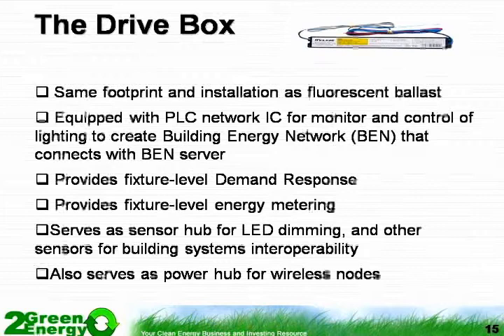We'll have a tiny logic power supply that will drive the PLC chip, as well as provide power to other sensors that we can plug into with Ethernet standard RJ45 connectors. And so we'll be able to dim at the fixture level, so each fixture can have its own dimming policy and be demand responsive, or be dimmed through sensors.